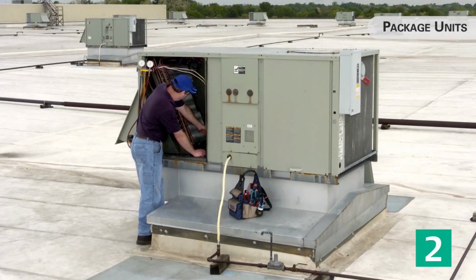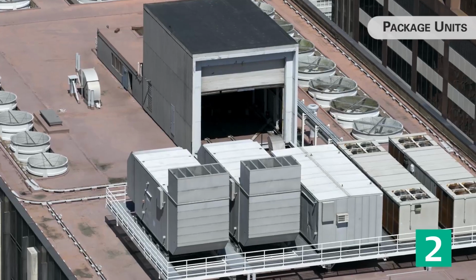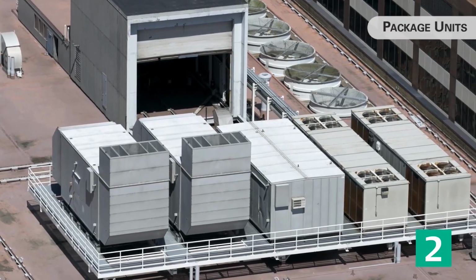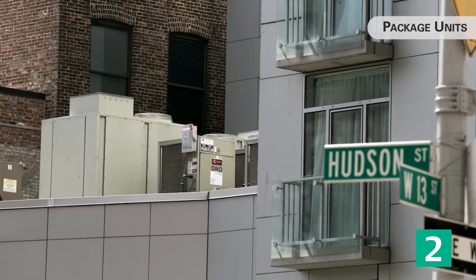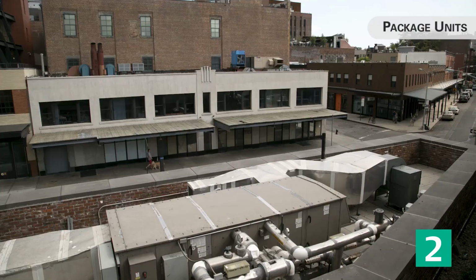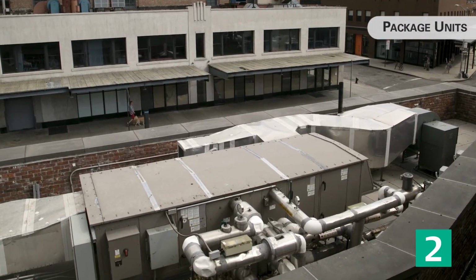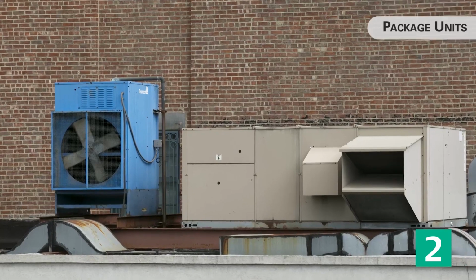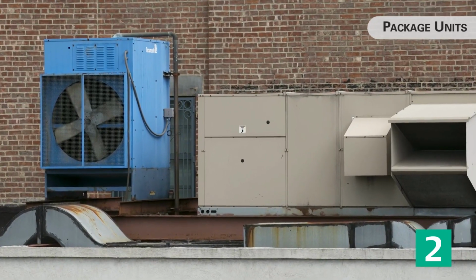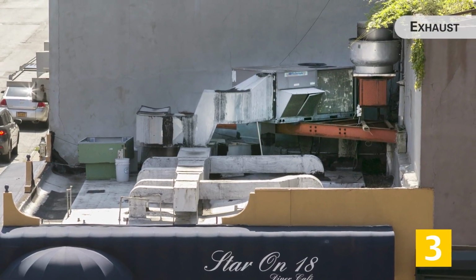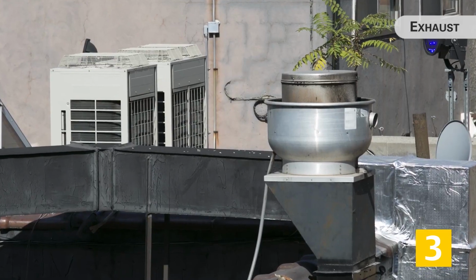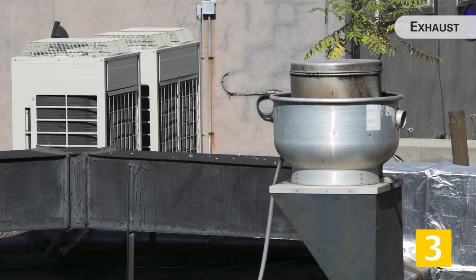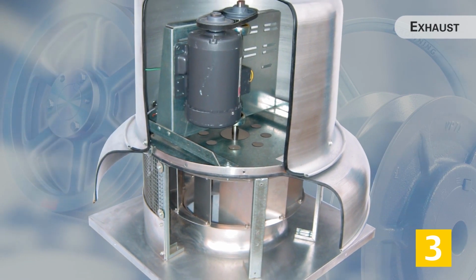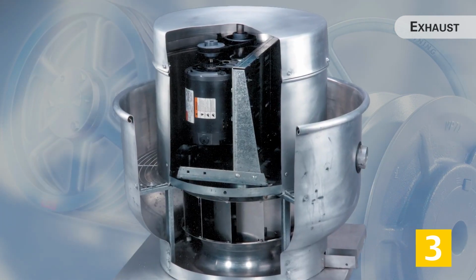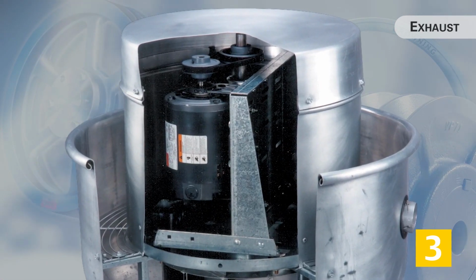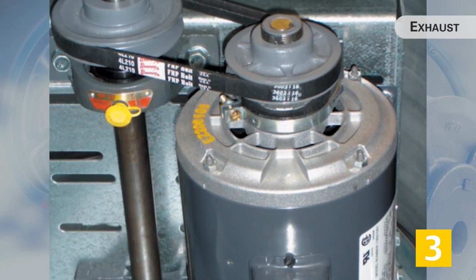Package units are used as part of the HVAC system. They are self-contained with all the components used to pull air from the occupied space, filter, cool, and then blow it back into the area. These motors can range from 5 to 30 horsepower depending on the size and demand of the units. Up and down blast exhaust fans are commonly found in commercial cooking applications. They are used to pull hot air, smoke, and grease through a hood away from the cooking area and out of the building. They're typically 1 horsepower or less.